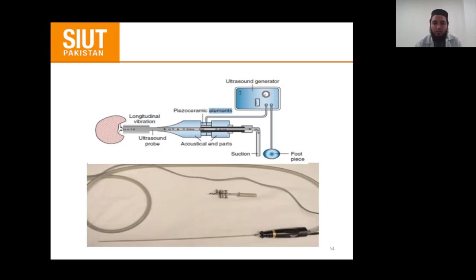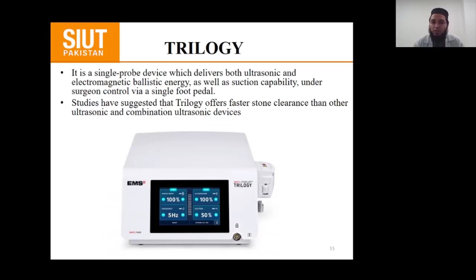So what is Trilogy? It is a single probe device which delivers both ultrasonic and electromagnetic ballistic energy as well as suction capability. So there are three options available: ultrasonic, electromagnetic, and suction capability, under surgeon control via a single foot pedal. Studies have suggested that Trilogy offers faster stone clearance than other ultrasonic and combination ultrasonic devices.